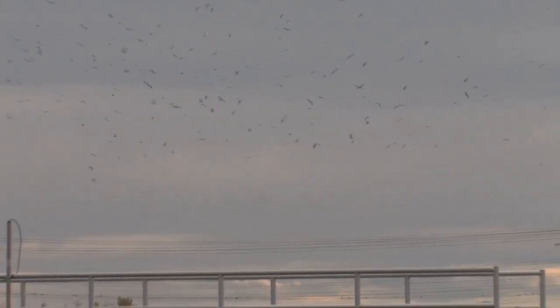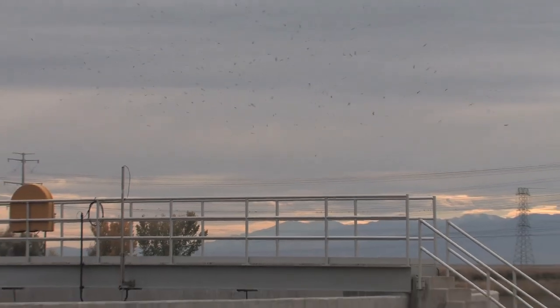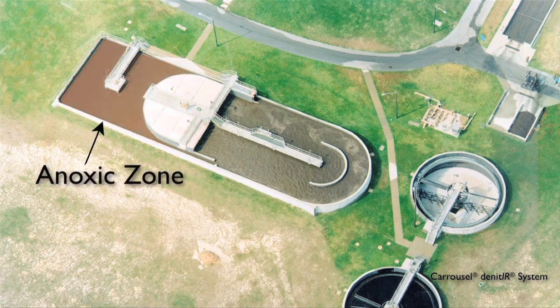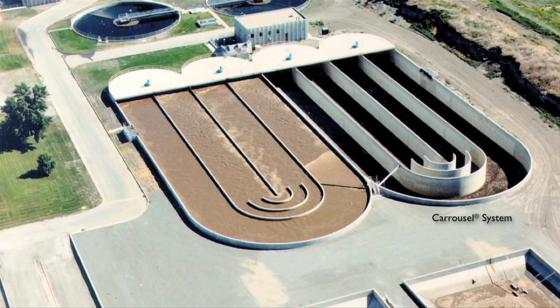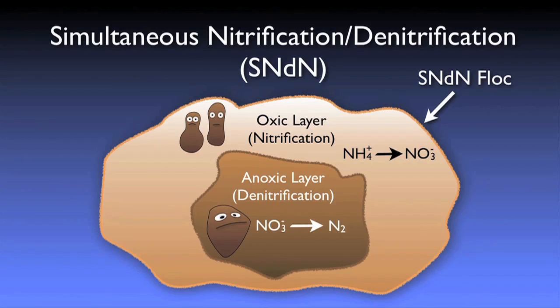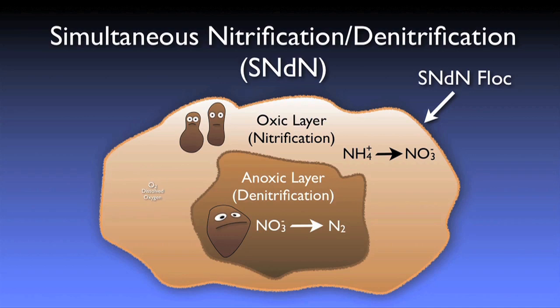There are many alternative strategies for developing anoxic conditions. Some treatment plants are designed to have dedicated anoxic zone volumes in the flowchart, while others strive to develop these anoxic zones within the oxidation ditch or aeration zone by rigidly controlling aeration or by turning off aerators for set periods of time. Additionally, under certain conditions, micro-anoxic zones can be developed within the bacterial flocs themselves, resulting in what is referred to as simultaneous nitrification-denitrification.